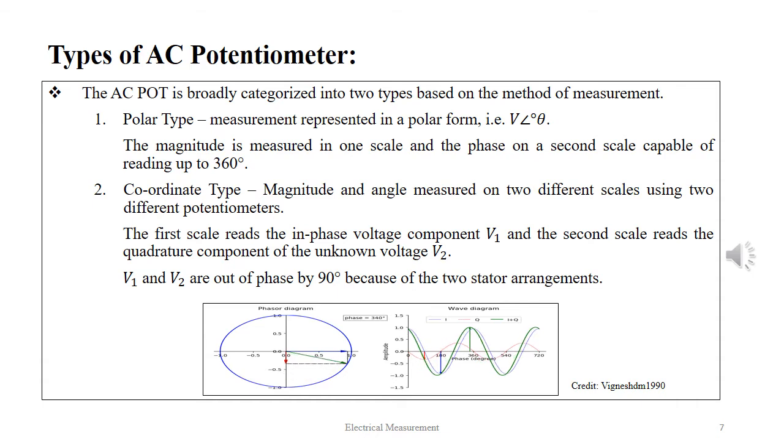And secondly, coordinate type. Magnitude and angle measured on two different scales using two different potentiometers. The first scale reads the in-phase voltage component V₁ and the second scale reads the quadrature component of the unknown voltage V₂. V₁ and V₂ are out of phase by 90° because of the two stator arrangements.